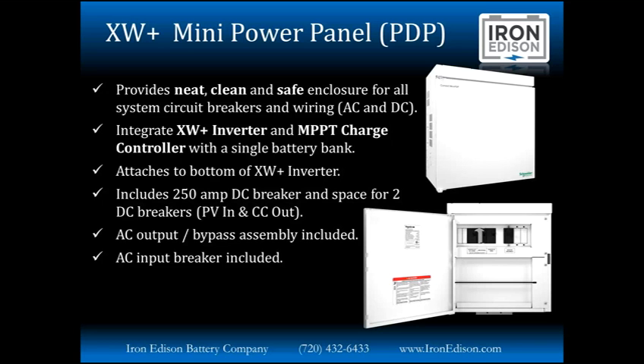I had some difficulty getting my head around it when I first got into this industry. Basically, it is an output selector. That's how I look at it. There's two breakers located there, one of them for the inverter output and one of them for the generator. And you can basically select what you want to have powering the loads downstream of the inverter.